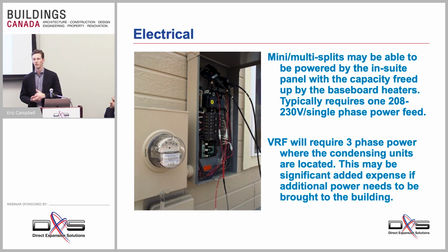On the flip side, VRF typically requires three-phase power, and that's going to be power up on the roof. It's going to be in a centralized location. If you have an electrically heated building that didn't have any of that central power feed, you're going to need to find power or provide extra power to the building, something that Toronto Hydro or whatever utility are can help you figure out. But you will need to supply that infrastructure in order to power those condensing units on the roof. Additionally, you will need separate power for all of your fan coils in the spaces, but those typically could be powered by your suite panel.